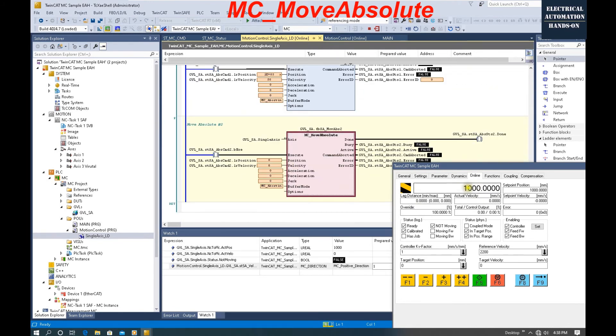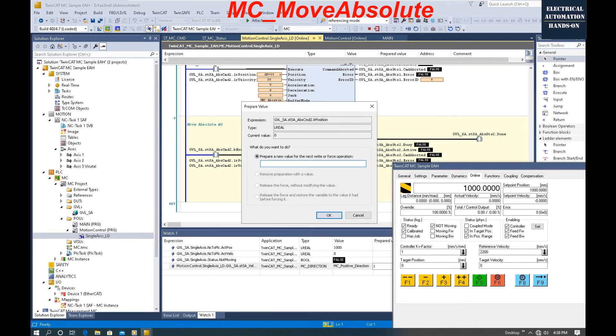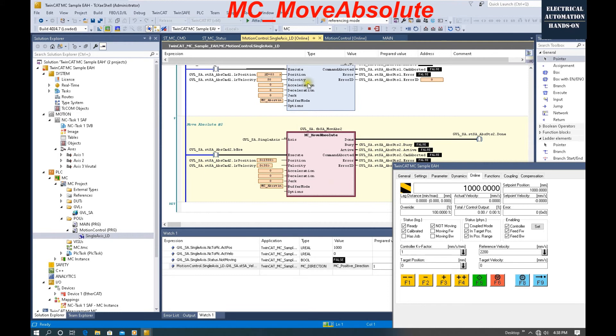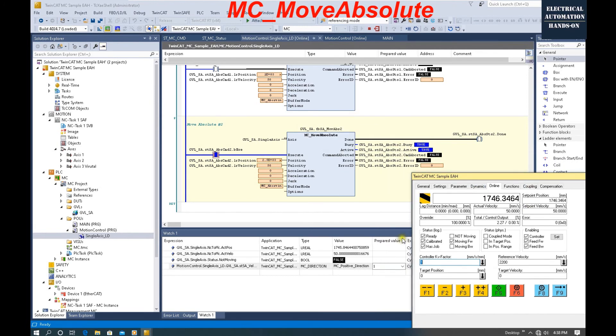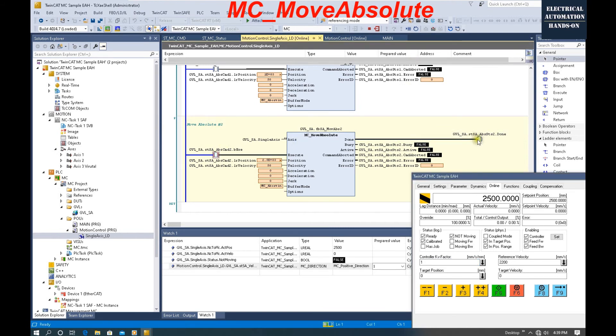For the next move, we are now at 1000. For the next position target, let's set 2500, and speed let's set 50. Once I trigger it, it will run to absolute position 2500. Trigger — busy and active are on, and the axis is moving towards 2500. From here, we can see the actual position feedback and actual velocity running. Once we receive the done signal, we can reset this command. Once it's reset, the done signal will also go off.